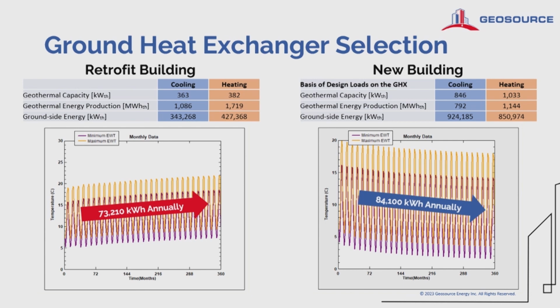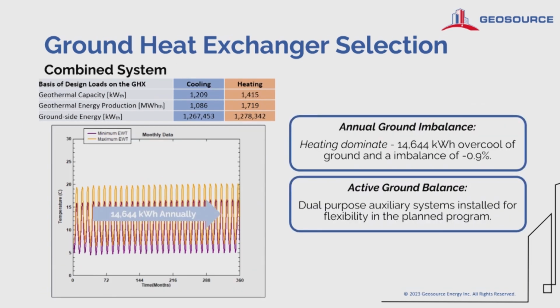In contrast, the new building is predicted to have a heating dominant building profile from the ground perspective. This has the opposite impact on the ground, cooling it over time, but with similar results, meaning that the efficiency will drain and eventually become inefficient over time. Now, although each of these systems is independently imbalanced on its own, we can see that they're imbalanced in opposite directions and at similar magnitudes. This means that we can combine these systems to deliver one combined system at a reduced capital cost for the client, and also produce a system with a much higher chance of being balanced organically.